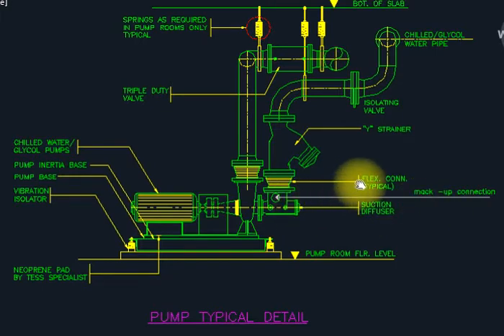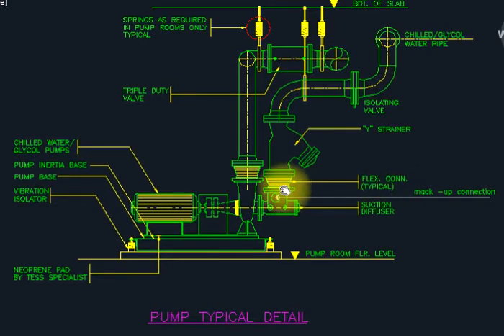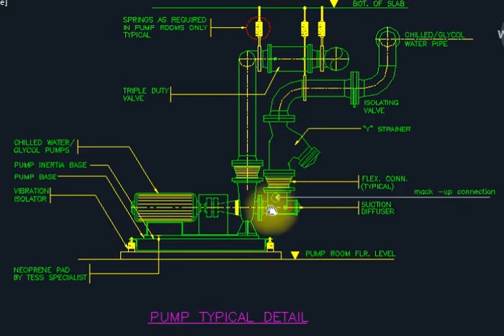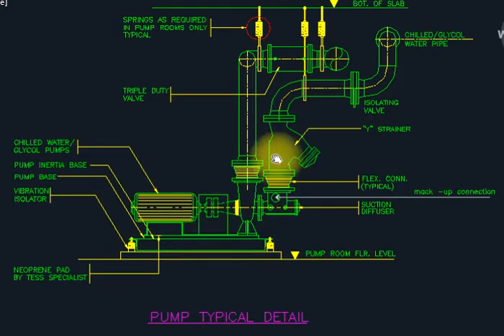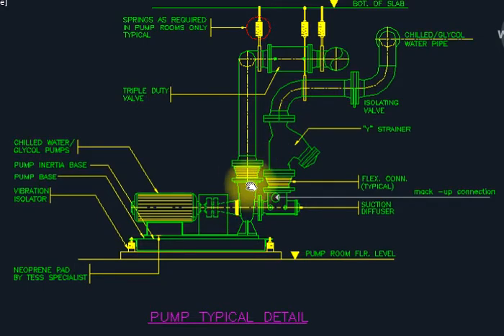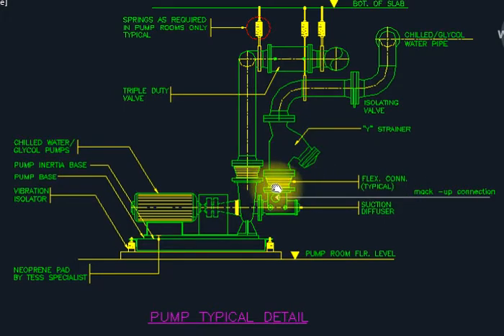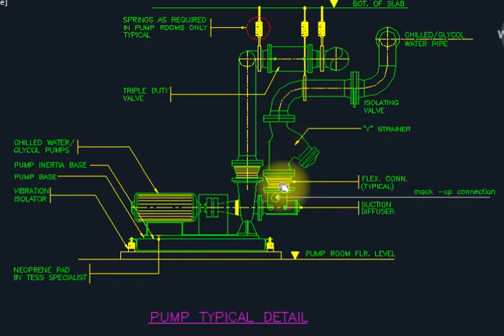We need a flexible connection here — a spring-type flexible connection or a rubber connection. This is because the pump vibrates, and without a flexible connection it can damage the pump or the pipes due to vibration. We must provide a flexible connection as per the standards.